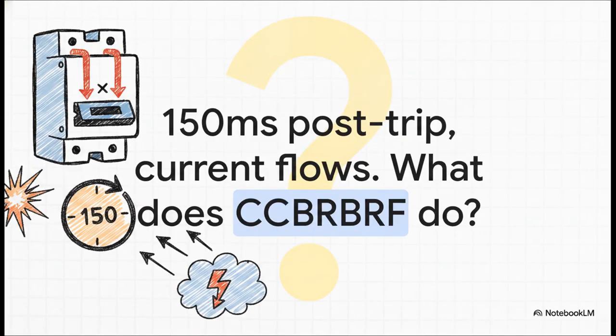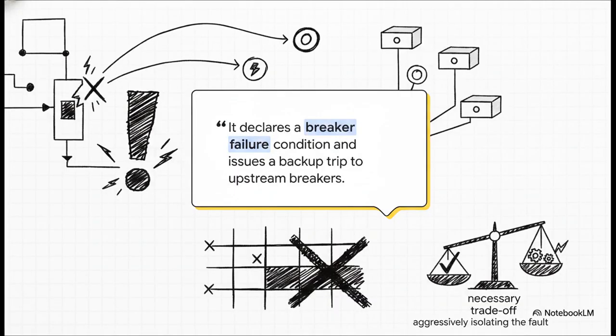Let's put this logic to the test. A trip command goes out. Fast forward 150 milliseconds, which is well past the normal operating time of a breaker, and significant phase current is still flowing. What exactly does the CCBR-BRF function do right at that moment? Exactly that. It officially declares a breaker failure condition and immediately issues a backup trip command to the upstream breakers.